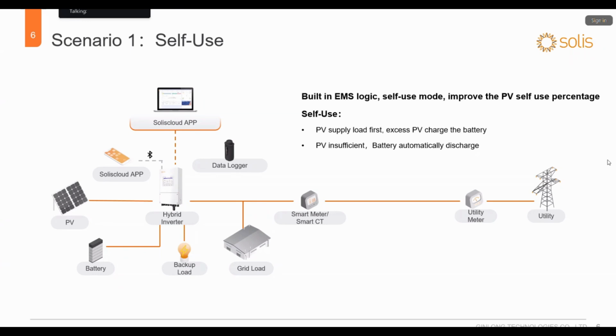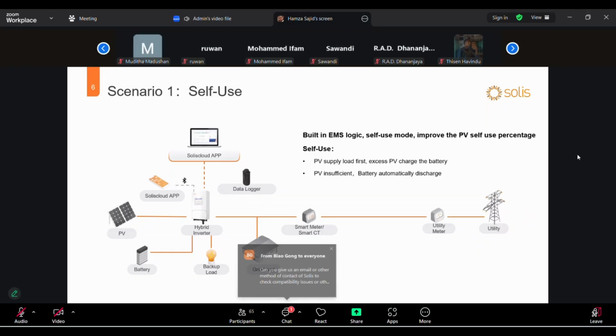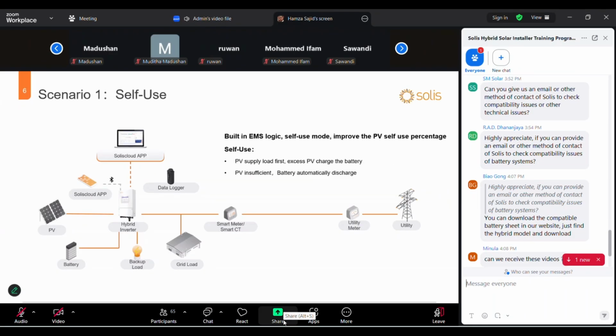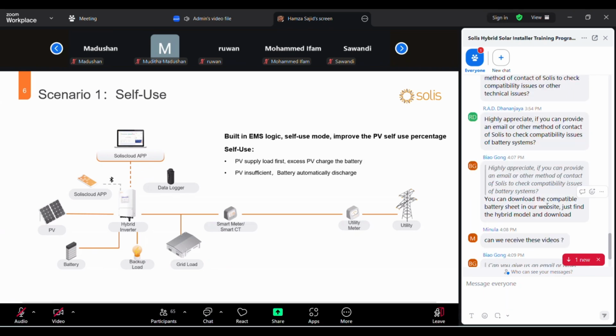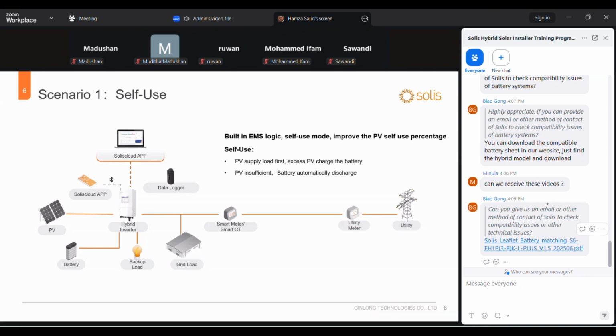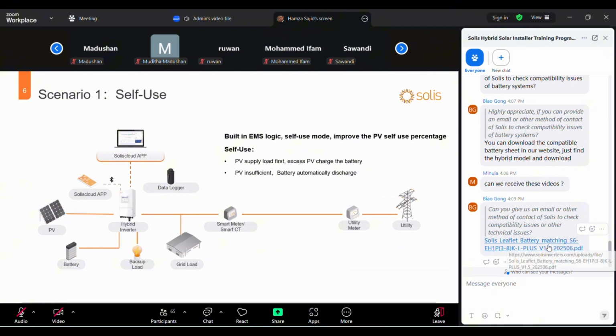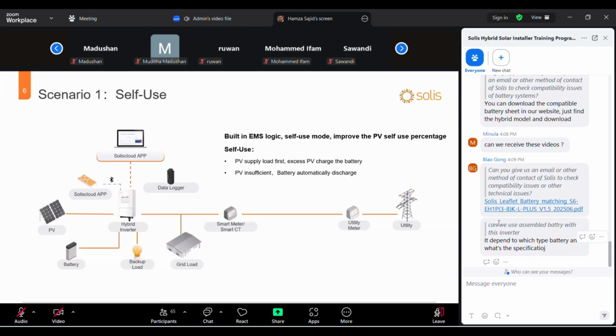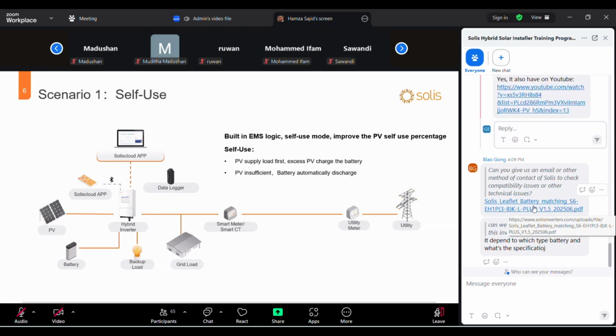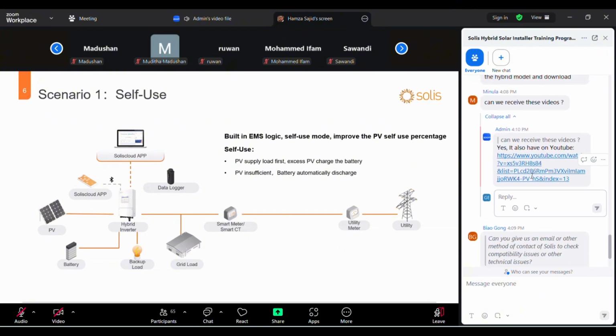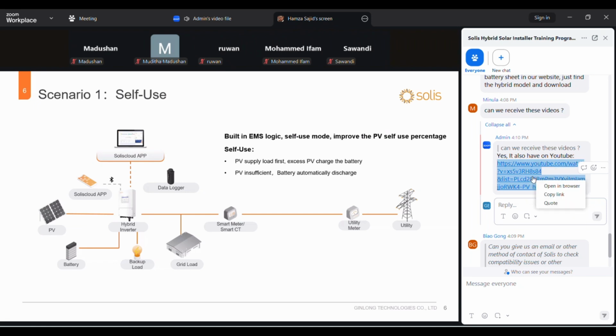So for all particular cases in a hybrid system, would it be possible to limit the input power from the utility consumption based on the PV input? It could be useful for meeting specific requirements. Yes, you can fix the limits from the consumption of the utility. You can use the peak shaving function, and there are charging and discharging options available in the settings. If you want to charge the battery with certain limits, you can set the charging current there.